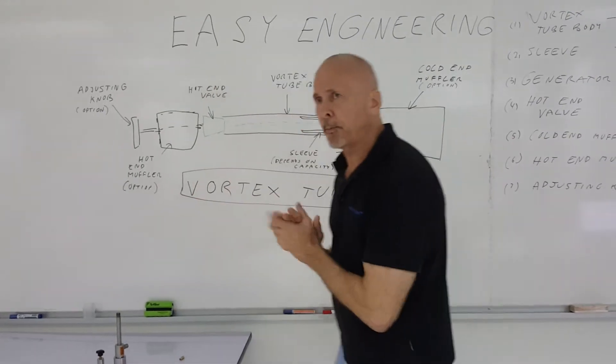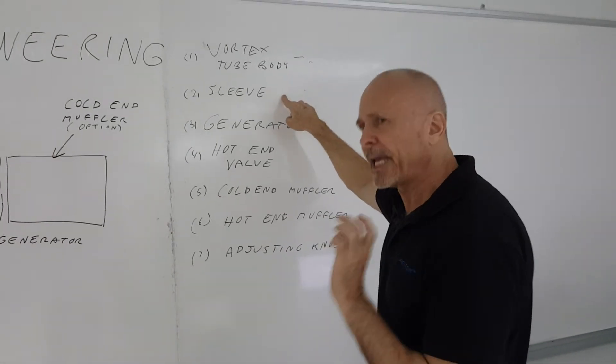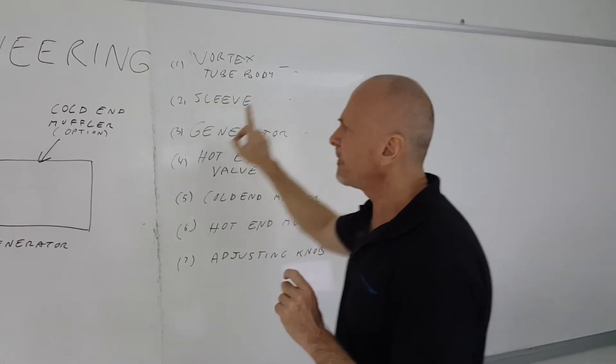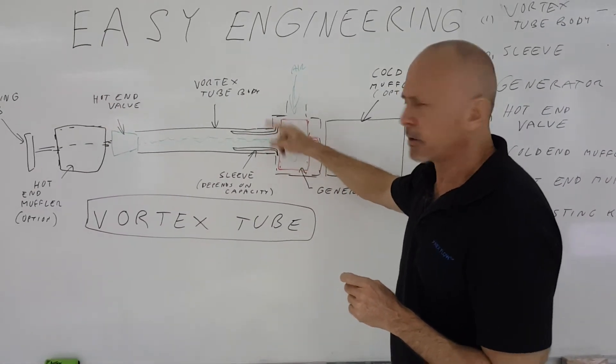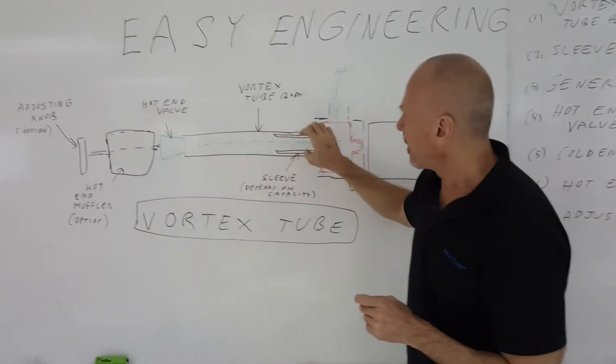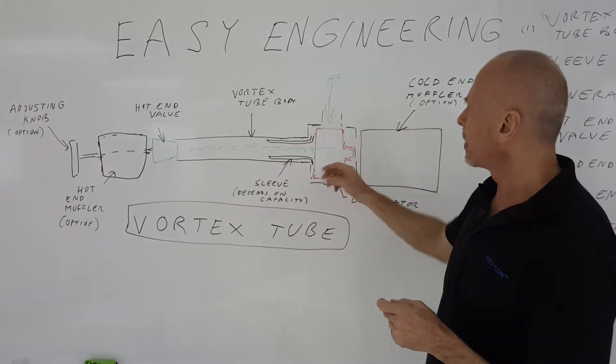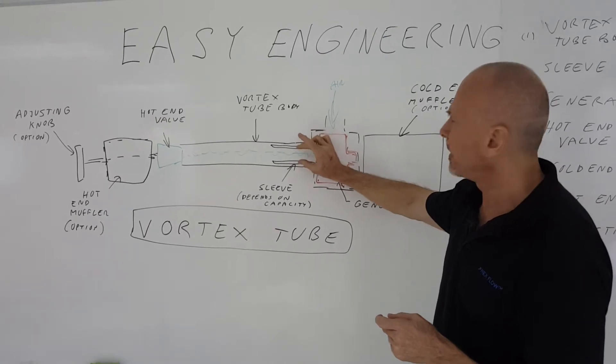So basically the parts of a Vortex tube are: Vortex tube body. You also have a sleeve occasionally put inside the Vortex tube body. The sleeve kind of controls the inside diameter a little bit of that hot area, of that hot end tube where the air is spinning. If the capacity is very low, you want to have that more narrow on the inside.